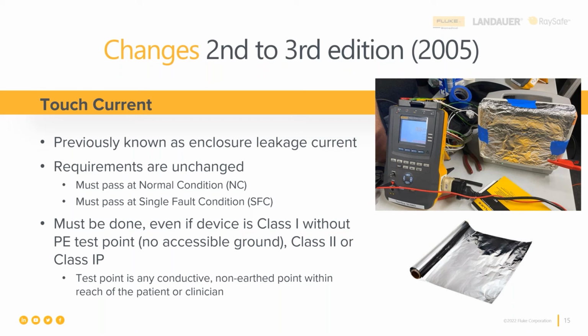And this test, as I said, must always be done regardless of the class of the medical device, regardless of whether we have a ground pin or no ground pin. It still has to be done, this test, the touch current test. And it's called touch current because the patient is touching the medical device, or the nurse or the doctor is touching the medical device and touching the patient.